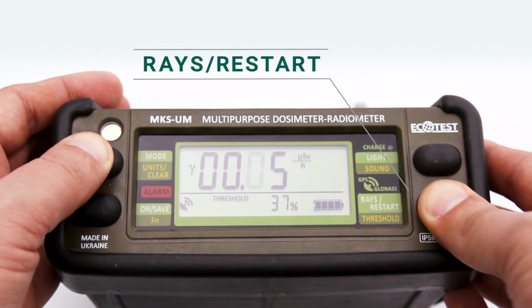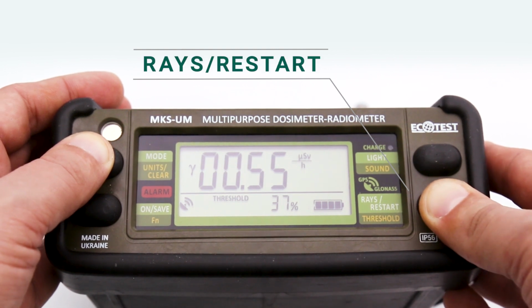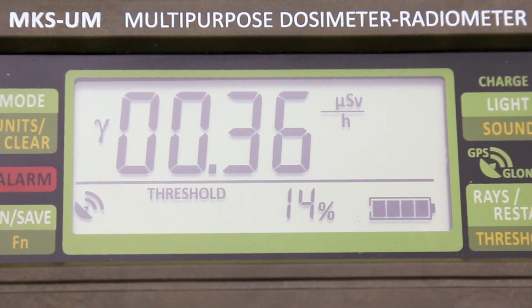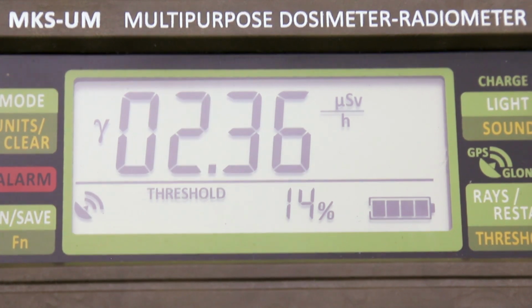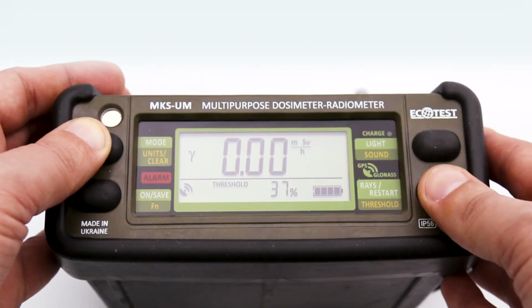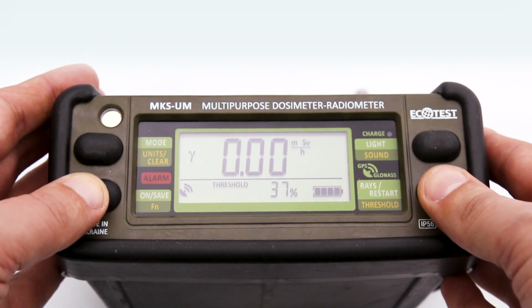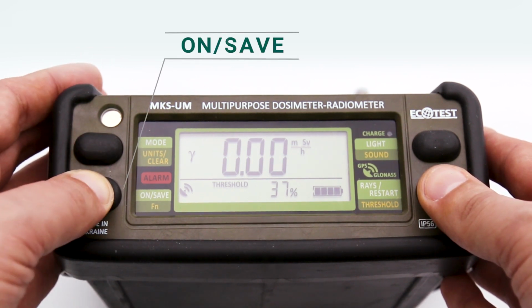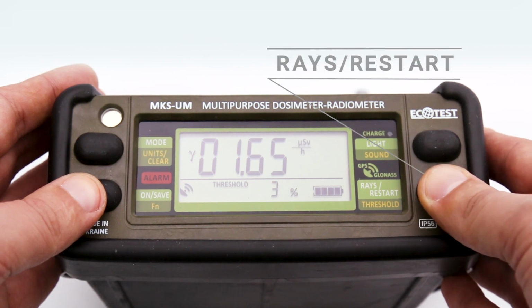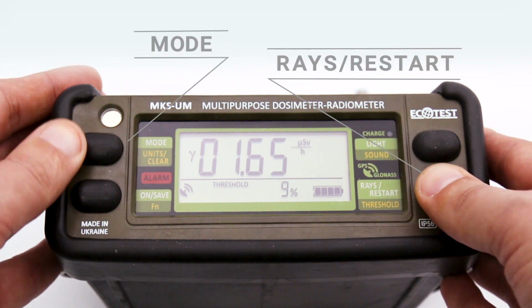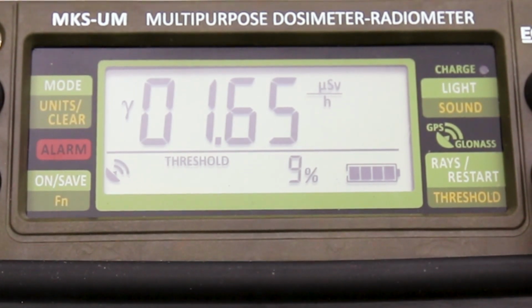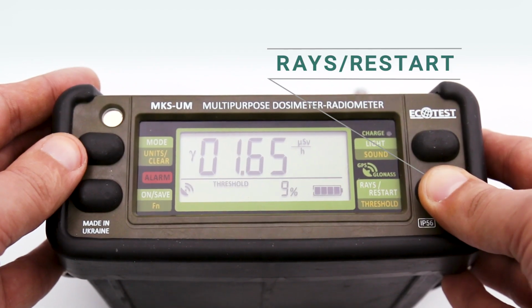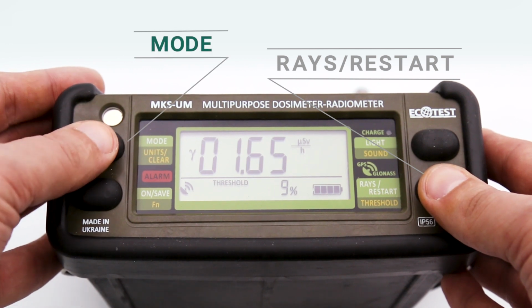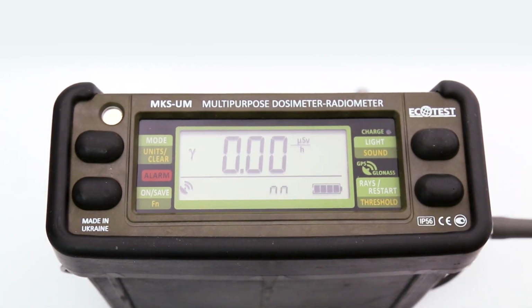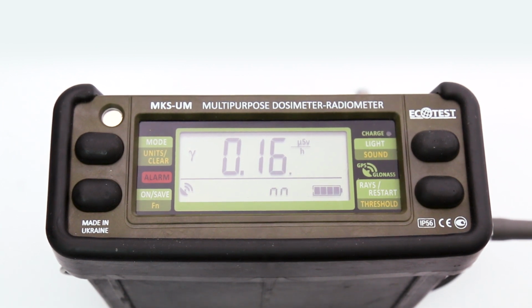This digit will stop flashing and the next one, ready to be changed, will start flashing. You can set the values of the other digits in the same way. If there is no need to set all the digits of a threshold level, press On Save briefly to save the threshold level and move on to setting the statistical error values in the same way. The set values of the threshold level and statistical error will flash 3 times on the display. This indicates that they are recorded in the memory of the control panel.